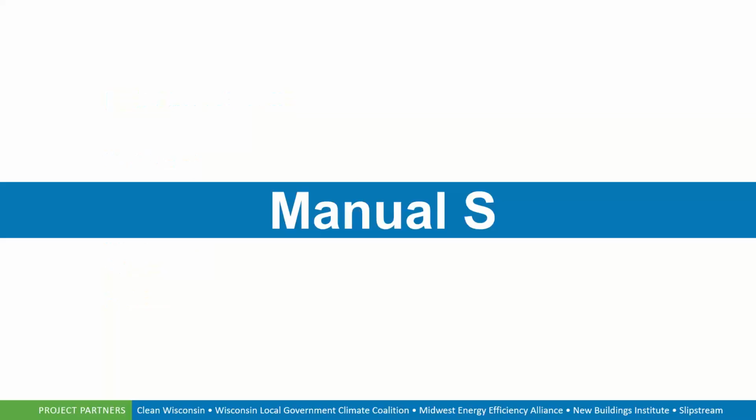So now we get into the Manual S. We've gone through the process of gathering all the information of the plans. We've done a plan takeoff to know each of the different room sizes within the house, including walk-in closets and bathrooms, areas that we know maybe have a heated or cooled assembly or register to those. Again, this is best practice, to get that shape of that room, that model built. We're going to take that number.